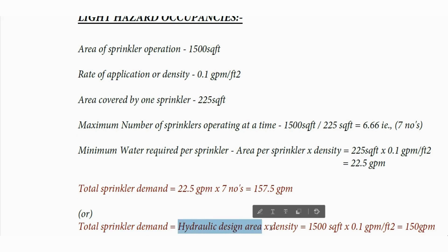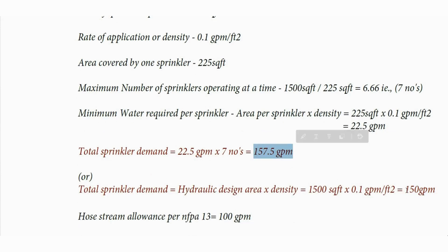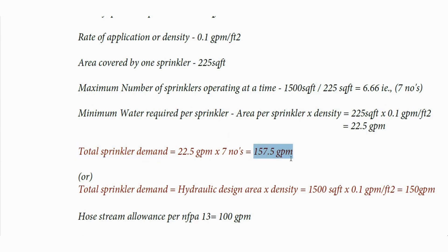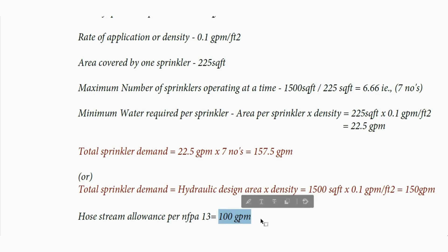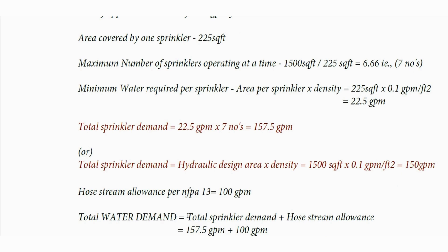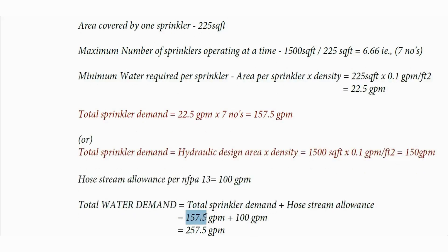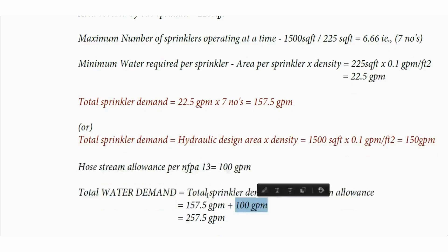The total sprinkler demand can also be calculated from the area-density curves using the formula: hydraulic design area multiplied by density. So 1500 multiplied by 0.1 equals 150 GPM. Since the demand based on number of sprinklers (157.5 GPM) is higher, we use that value. We then add the hose stream allowance — for light hazard, the combined inside and outside hose is 100 GPM. Therefore, total water demand is 157.5 GPM plus 100 GPM, equaling 257.5 GPM.